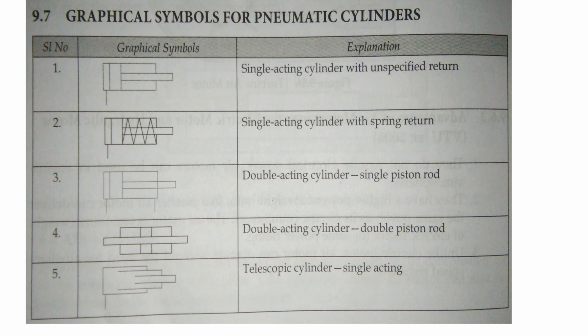Then next we have two inputs, or you can see two dotted lines, one at the piston and one near the rod. That indicates the double acting cylinder. Next we have the full length of rod on both sides. This is called a double acting cylinder with a double piston rod. So both sides will have the piston rod. Application wise, both sides of the rod can be used for to-and-fro motion. Instead of giving only one side, both ends can be connected.